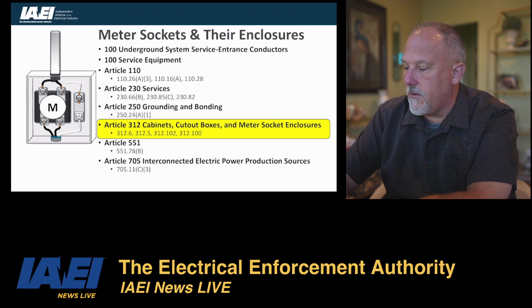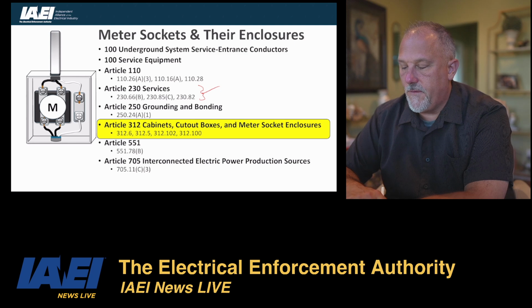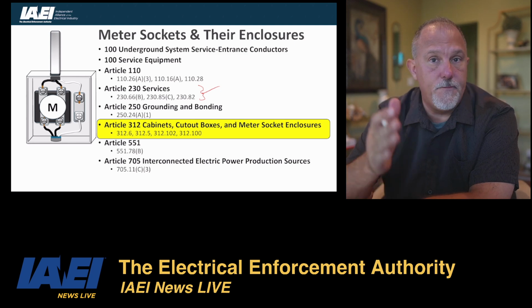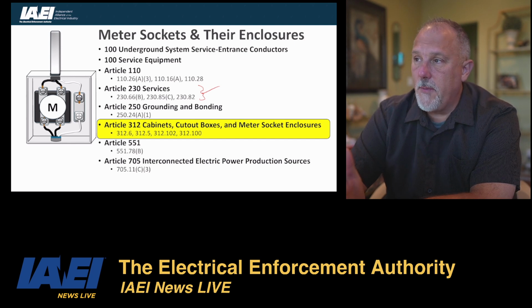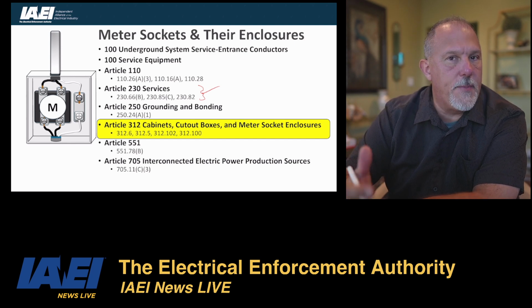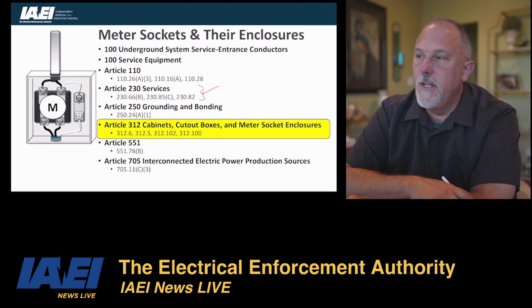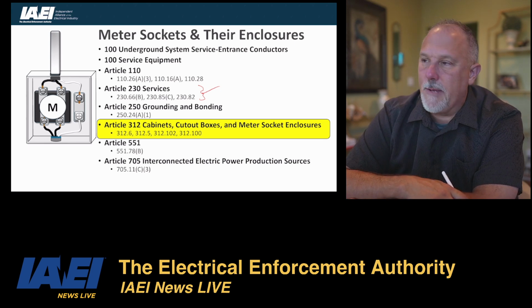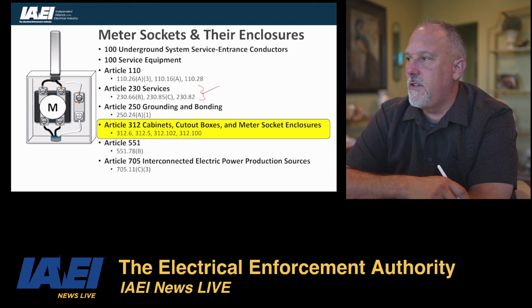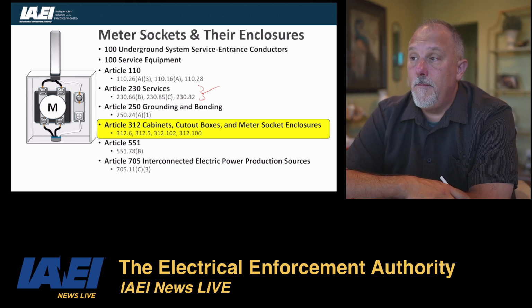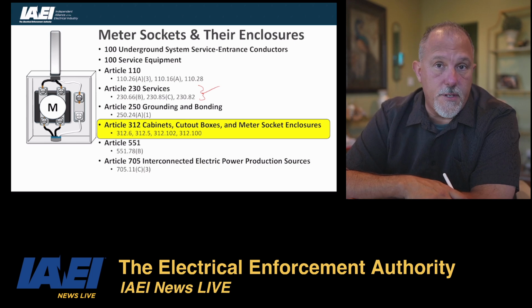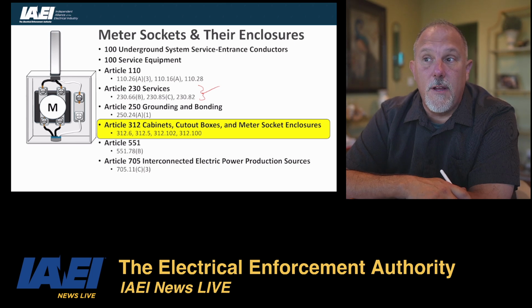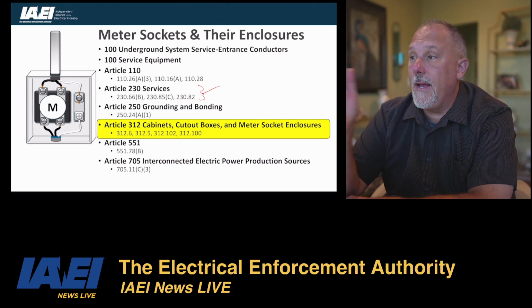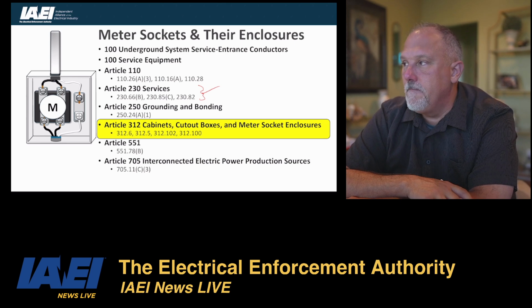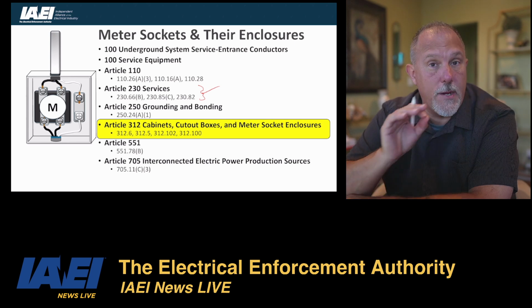In Article 230, you have 230.66(B), which we said is supposed to be a marking requirement, but it's not. It just tells you that it has to be listed and rated for the voltage and current of the service. And there is an exception that meter sockets supplied by and under the exclusive control of an electric utility are not required to be listed. So if that meter socket is under the exclusive control of the utility, the National Electrical Code doesn't even apply, and you don't even need that exception. But in any case, it's there for clarity.